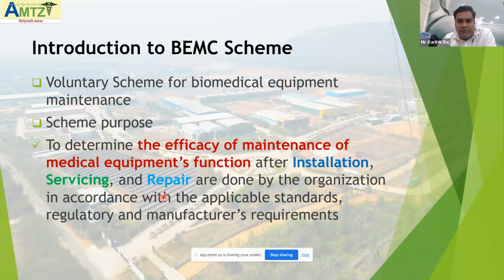So once you install the equipment and you do some repairing or maybe PPM, we don't know whether the equipment is in good condition or not. So this scheme is all about making sure that the equipment is in good condition. When we say good condition, it means it's safe to use, and the end user, whether doctors, nurses, or anyone touching the equipment, won't have any problem. So always the patient should be safe, and the person using the equipment should also be safe. That is why we came up with this scheme.